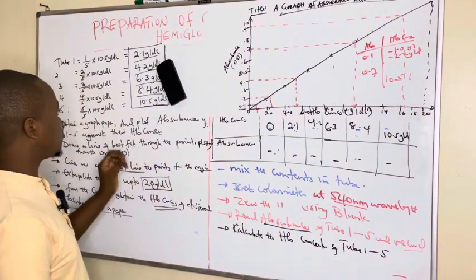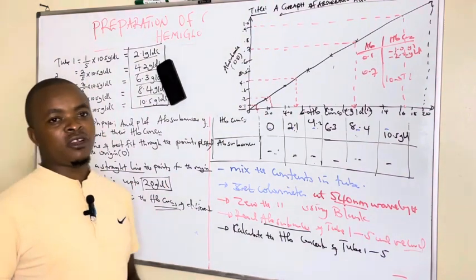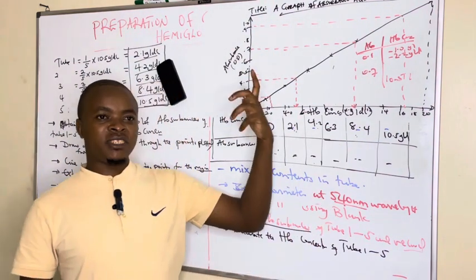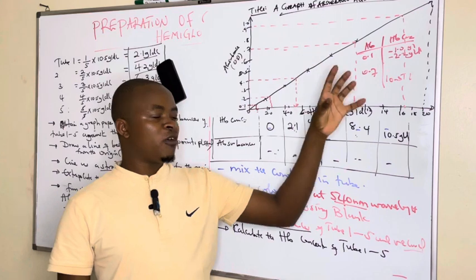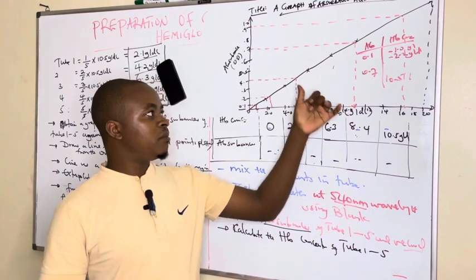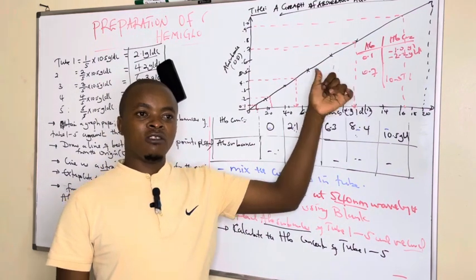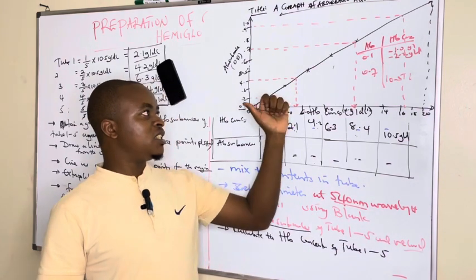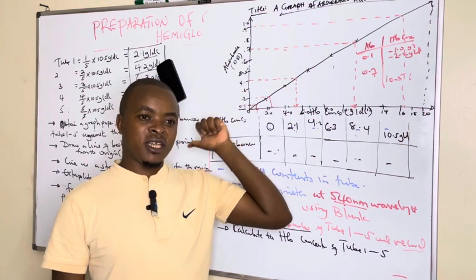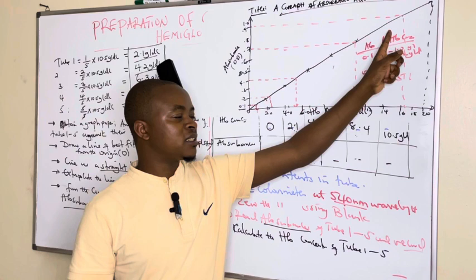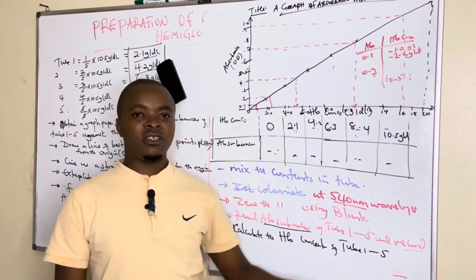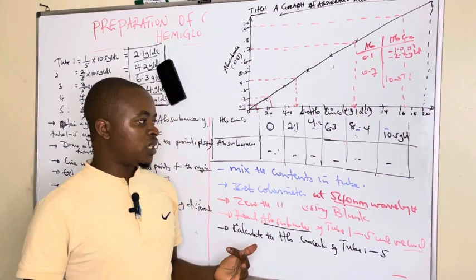All machines in the laboratory do this: every time we install a machine, we develop the calibration curve, and it is the machine that uses the calibration curve to come up with the values. The machine reads the absorbances or the optical density, and it matches them with this calibration curve to give you the results. This is what we can discuss today.